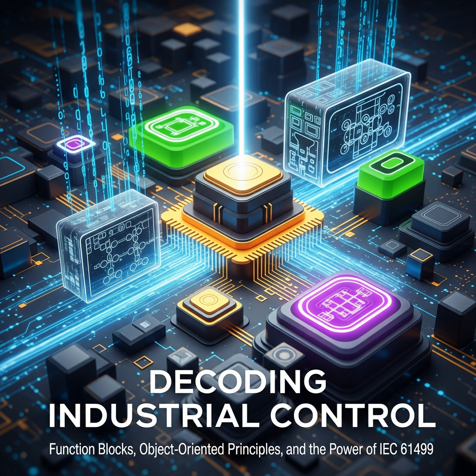It sounds like a lot of thought went into making these function blocks self-contained units. What's actually happening inside them? How do they manage their own logic, their own data? And why is that internal structure so important for the system as a whole, for things like reliability? That internal structure is fundamental to how they work and why they're robust. Inside, function blocks can hold internal variables, sometimes called state information. And unlike those temporary variables in basic FBs, these ones persist. Their values stick around between times the block's algorithms run. This is obviously critical for keeping track of what's happening in an ongoing industrial process.